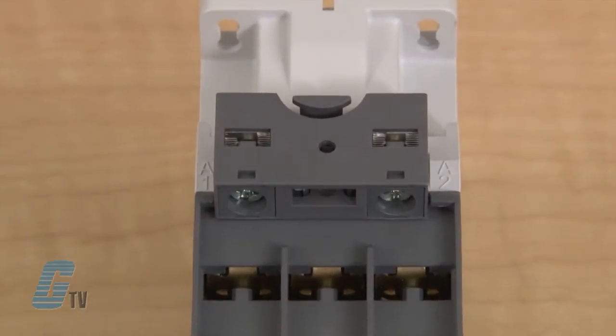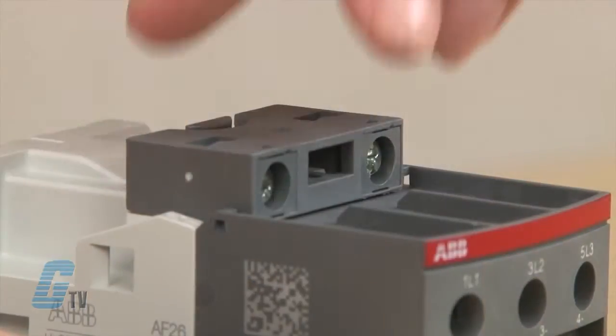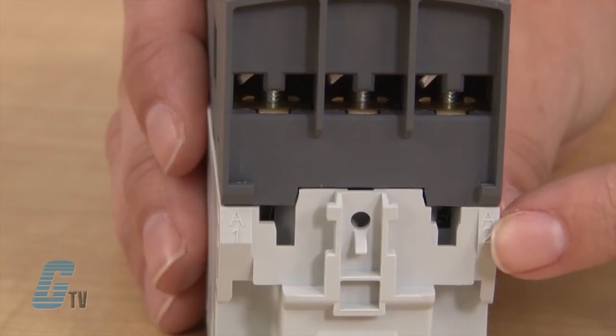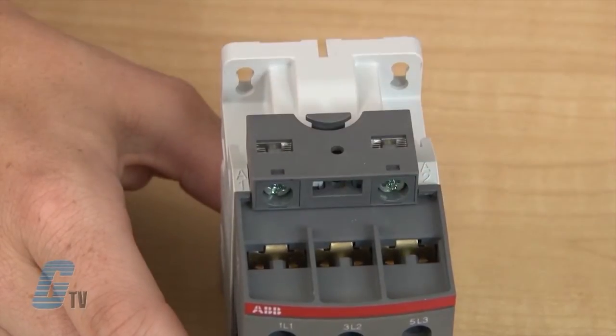On this series, a coil terminal block for A1 and A2 connections may be included on the top. This can be removed by pulling on the tab until it unlatches, where I can move the coil terminal block to the bottom if I would like to make my coil connection from underneath. I will keep this at the top by placing the pins at the A1 and A2 opening and then sliding the terminal block until it snaps into place.